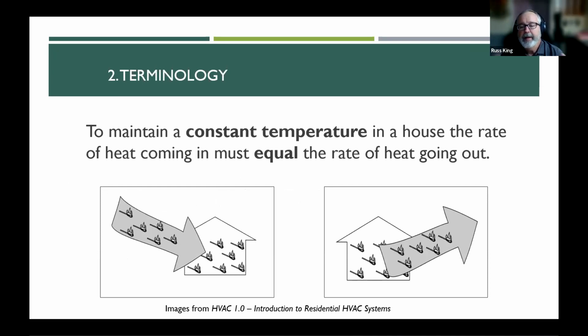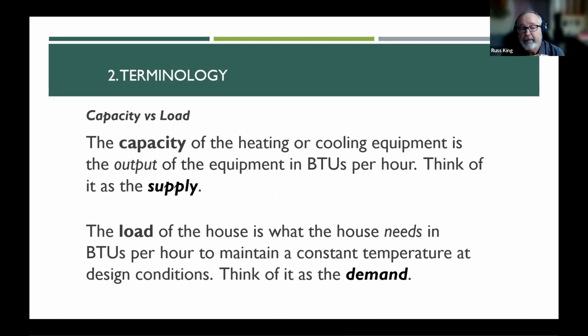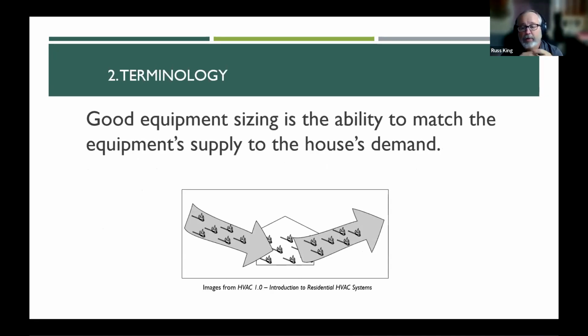All right. So to maintain a constant temperature in the house, the rate of heat coming in must equal the rate of heat going out. The capacity of the equipment is how much heating or cooling it provides. Okay, so think of that as the supply. You've got supply and demand. Supply is what you're getting from your equipment, whether it's the heater giving you BTUs, and demand is what the house needs. Supply could also be how many BTUs of cooling it provides, and demand is what the house needs. So it's balancing those two things. Good equipment sizing is the ability to match the equipment supply, its capacity, to the house's demand, its load, whether it's heating or cooling.